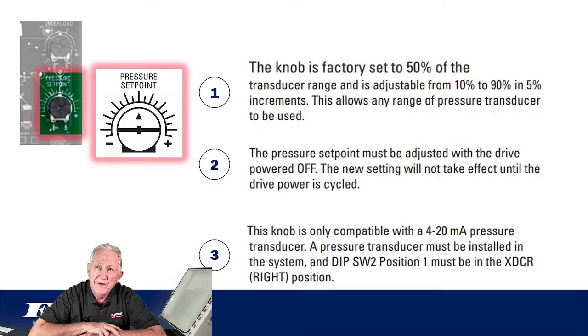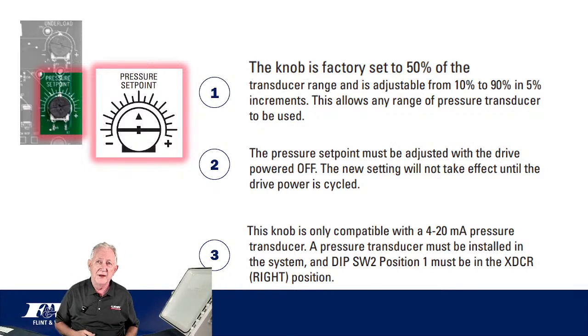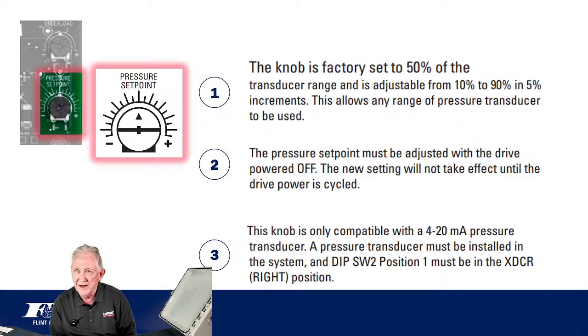So it's set at 50% of that range. 50% of that would be right at 50 PSI. If it's a 100-pound transducer, it's going to be set at 50 PSI. But this is adjustable. You can adjust it from 10 to 90% of that range. Again, this is of the range of that transducer. So that's 10 to 90% of that 100-pound transducer. What did that just say? You can go from 10 PSI to 90 PSI, and you can do that in 5 PSI increments.